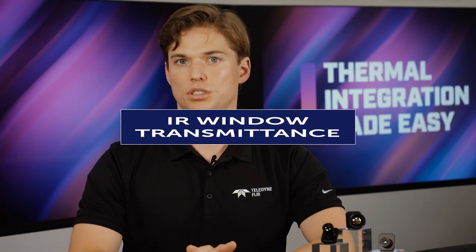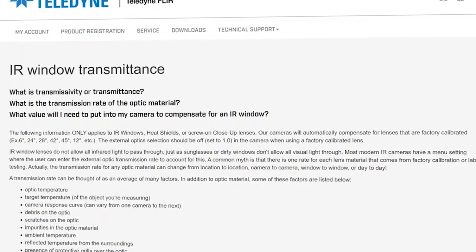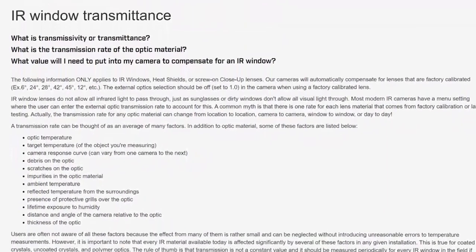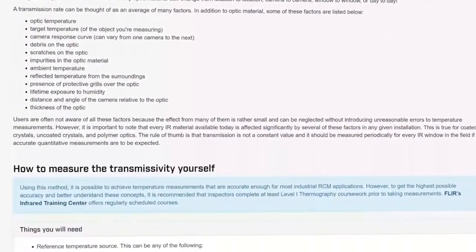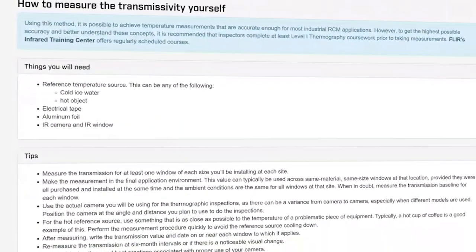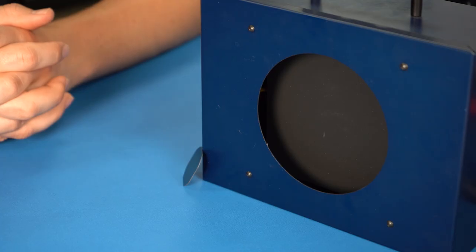Please see the IR Window Transmittance procedure found at the FLIR CustHelp support site. This procedure covers the definitions of transmissivity or transmittance, what the transmission rate is of an optic material, and what values are needed to compensate for an IR window. There is a simple way to perform a quick window transmission test using the built-in Window Transmission Environmental parameter and a blackbody.